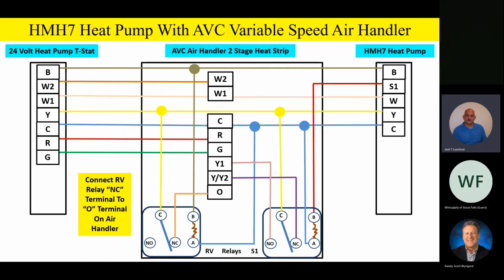So here's the deal. On any variable speed product, fellas, in the cooling mode of operation, for advanced functions like cooling on delay, dehumidification, some of these other things, the variable speed product has to have an O signal on a heat pump so it knows it's in the cooling mode. So let me say that again. On any variable speed product, whether it's a furnace or an air handler, we have to have O energized on the air handler or furnace to tell that unit it's in the cooling mode of operation. So on this product, we have to be able to provide that O signal in the cooling mode, and that's what we do with the RV relay.